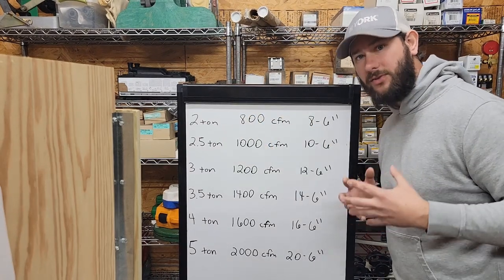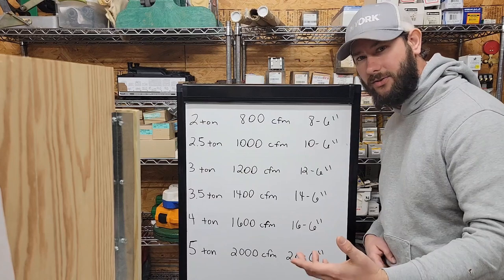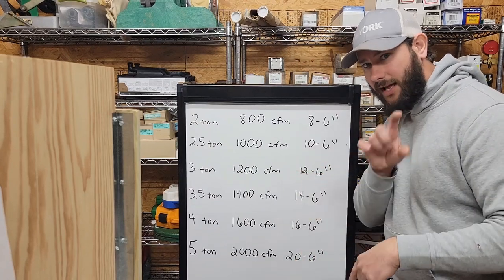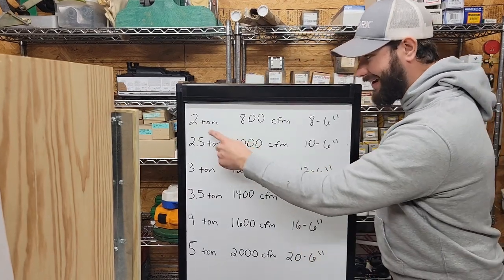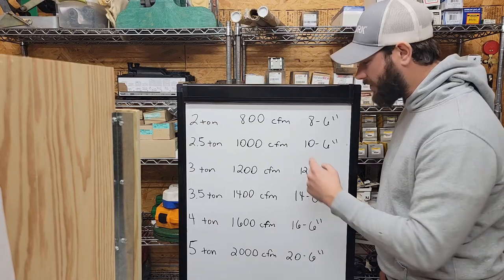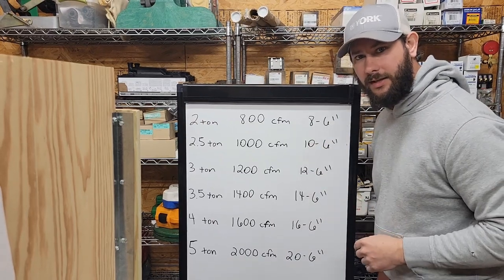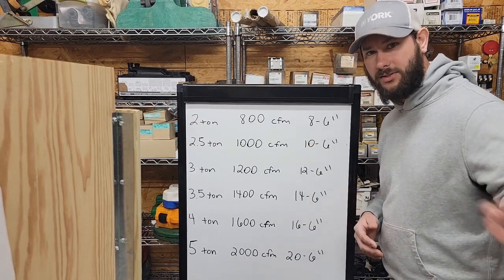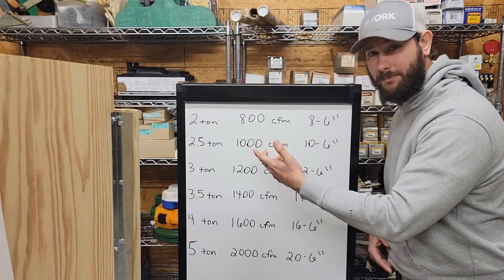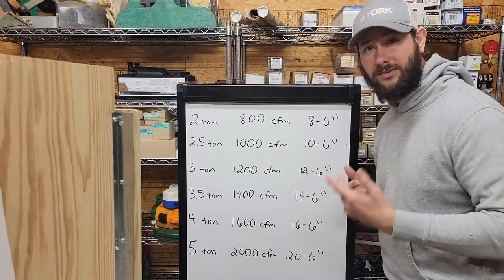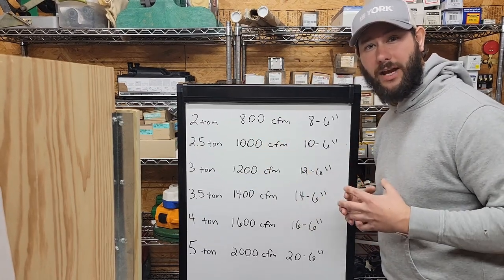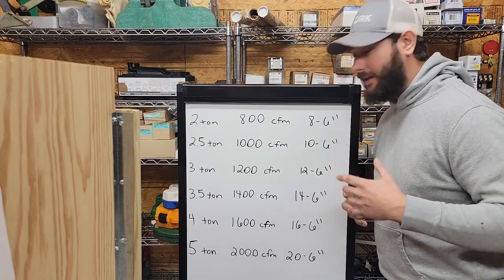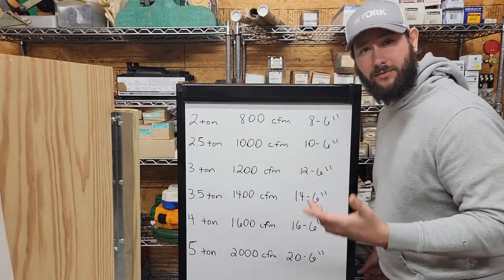unit. So now you kind of understand that when I go to a house and I'm looking at all the vents and then I look at the tonnage, I'm going, uh-oh, this 2-ton unit you have, sir, only has 4 lines. And we need to add some duct if we're going to install a new piece of equipment, especially a heat pump. I know the indoor coil is getting super hot and trying to reject heat during the heat mode, and we only have 400 CFM for this 2-ton unit.